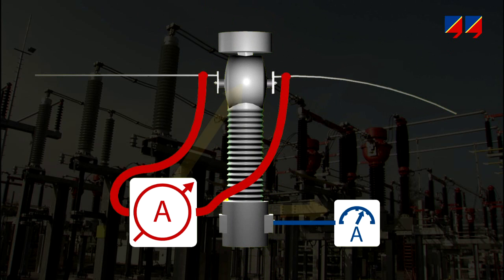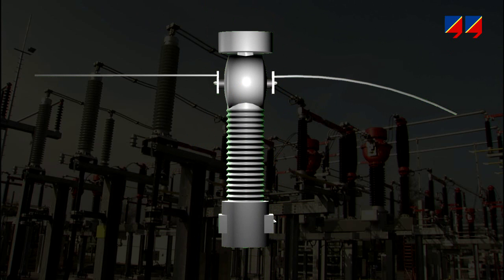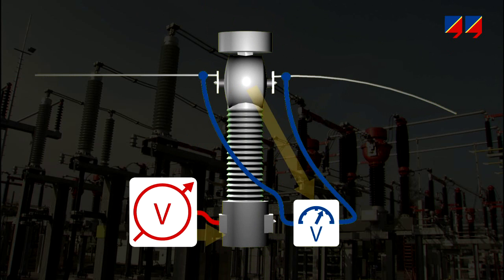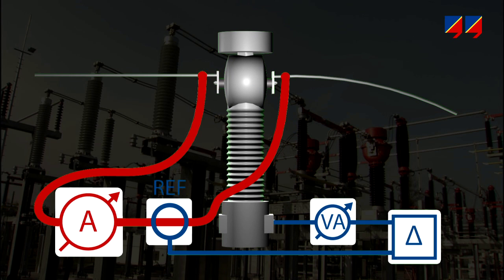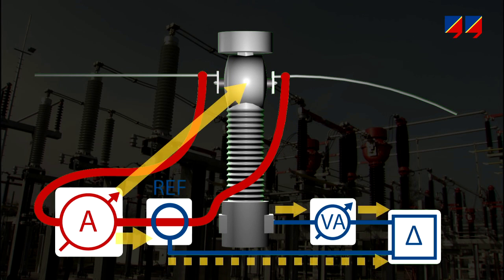The three methods are: primary current injection using a portable high current source; secondary voltage injection using a portable variac; and primary nominal current injection using a high current source, a reference CT, a burden simulator, and a bridge.